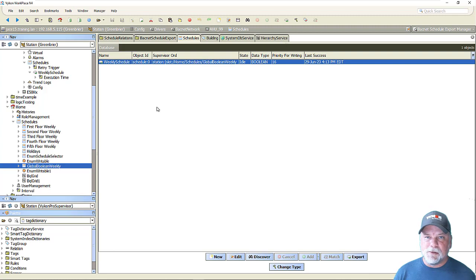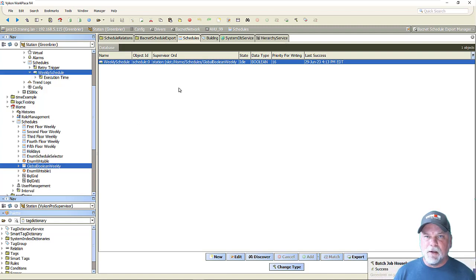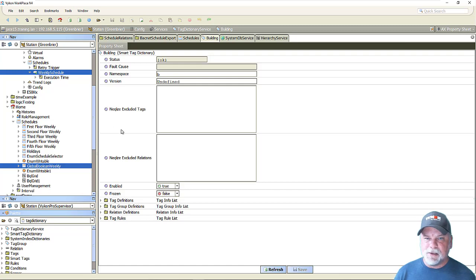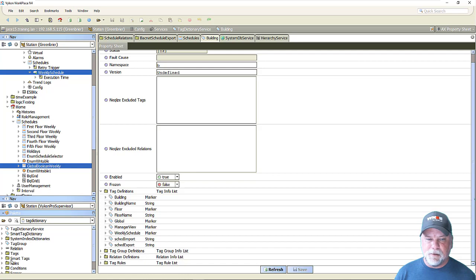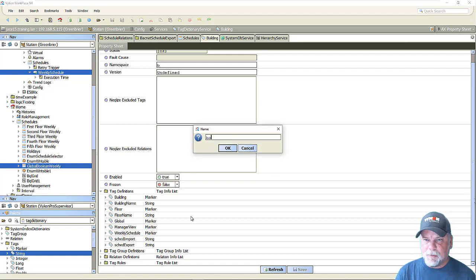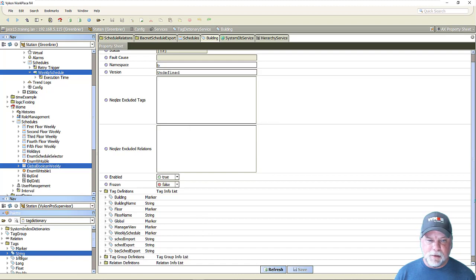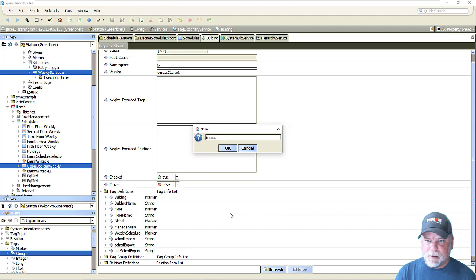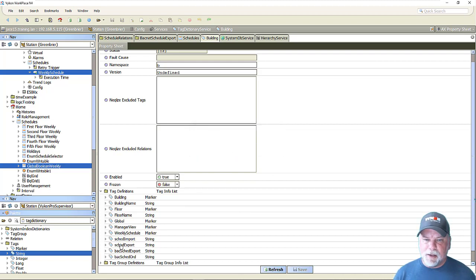So we need to put some smart tags on both this weekly schedule as well as this schedule device extension. The first thing we want to do is define some tags. Going over to my building dictionary in the J station, I'll expand the tag definitions here and using the tag dictionary, I'll drag in a string tag to define a tag so someone knows that it exists. I'm going to call the tag ID 'bacSchedExport'. We'll create another tag and call it 'bacSchedOrd'. I already have schedule import and schedule export tag definitions from the previous video and could potentially use those as well.